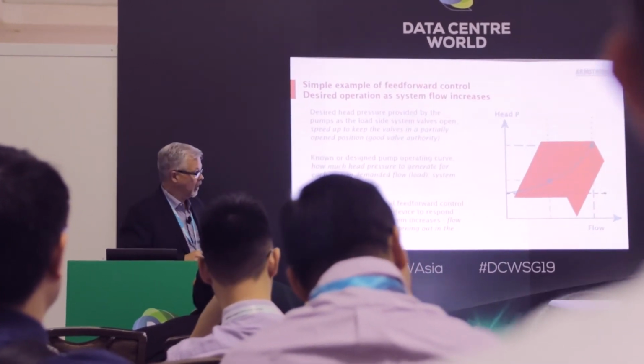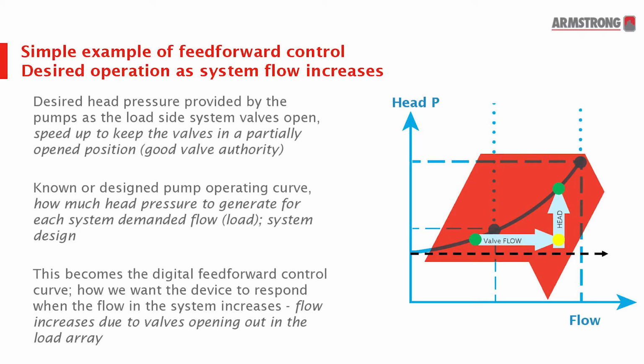So this would be our feed-forward control map for that pump. If we're starting at the green point, that specific load point, and as the cooling system starts to load up, the valve will open and it will draw more flow. Even as the pump stays at its original speed, the flow will increase through that pump. We'll see the power go up on the pump. It's related to flow. And we'll see that we're off our control curve.